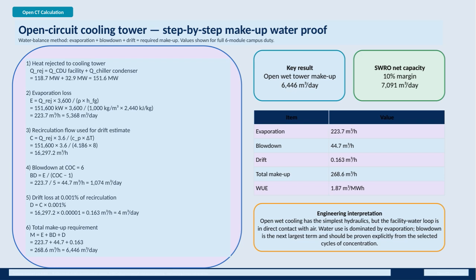From an engineering perspective, open wet cooling towers offer straightforward hydraulics, but the water in the facility loop is exposed to the atmosphere, making evaporation the dominant water loss. Blowdown also plays a significant role and must be accurately validated based on selected cycles of concentration. This comprehensive calculation equips us with a solid understanding of water needs for the cooling tower in this coastal data center environment.